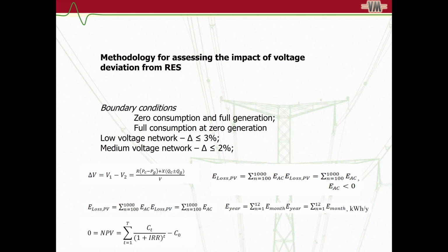So the voltage regulation range in the medium voltage substation is plus minus 400 volts, or this is 2%. In this sensitivity range, the automatic voltage regulation is not activated and the step controller does not switch. Of this permitted deviation of 10%, 5% remains for the distribution network, which in the absence of other rules is distributed.